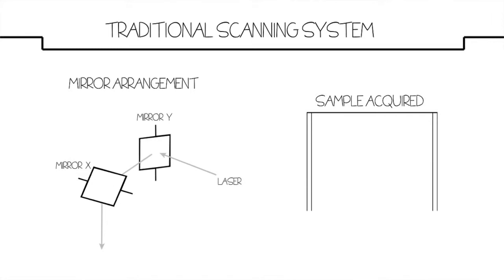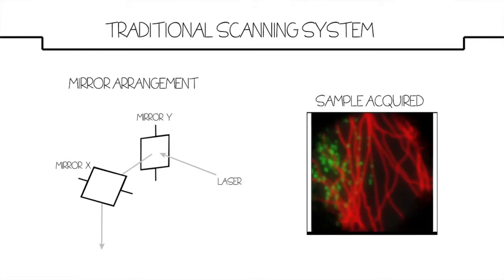However, these changes result in uneven illumination of the back focal plane and non-uniformity of field illumination, especially in the periphery. A common workaround is to restrict the acquisition area to the center of the field.